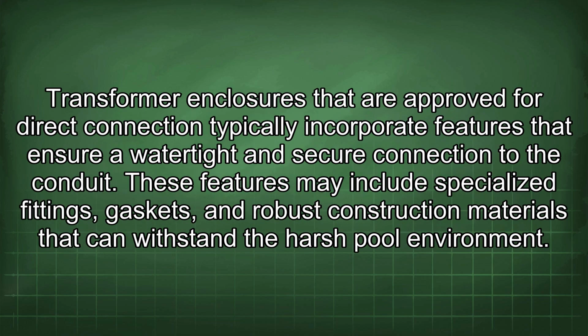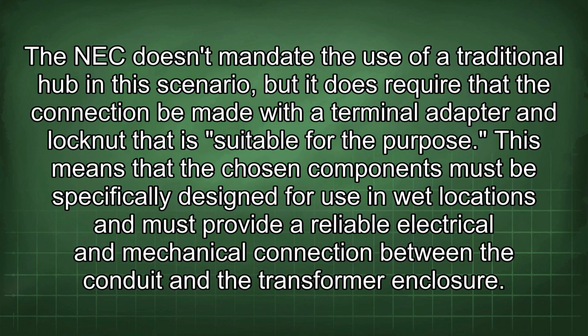Transformer enclosures that are approved for direct connection typically incorporate features that ensure a watertight and secure connection to the conduit. These features may include specialized fittings, gaskets, and robust construction materials that can withstand the harsh pool environment. The NEC doesn't mandate the use of a traditional hub in this scenario, but it does require that the connection be made with a terminal adapter and lock nut that is suitable for the purpose. This means that the chosen components must be specifically designed for use in wet locations and must provide a reliable electrical and mechanical connection between the conduit and the transformer enclosure.